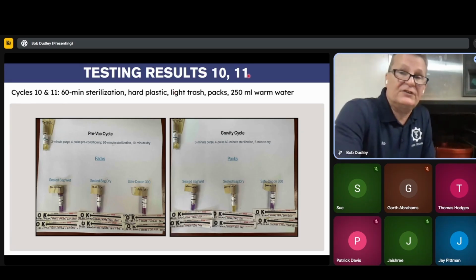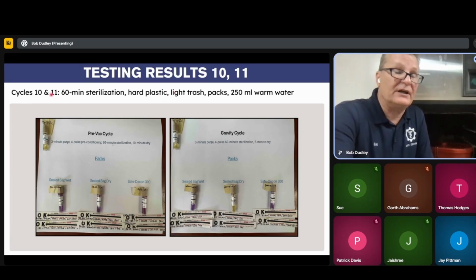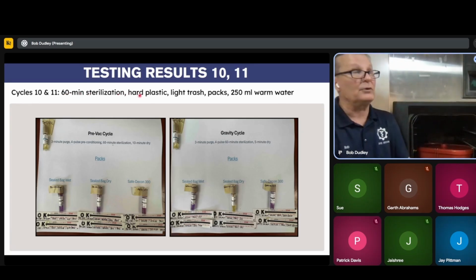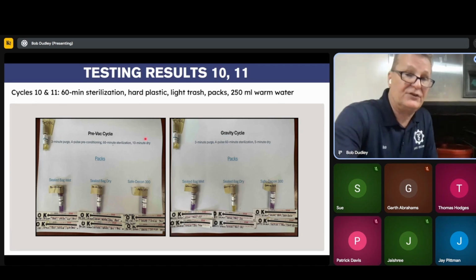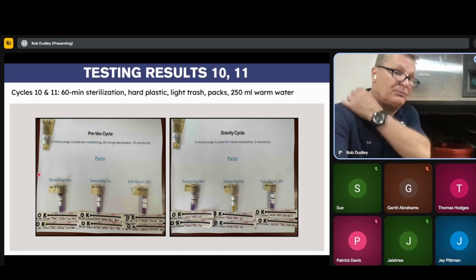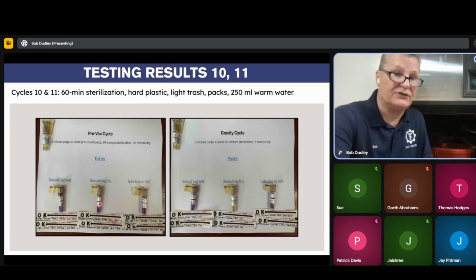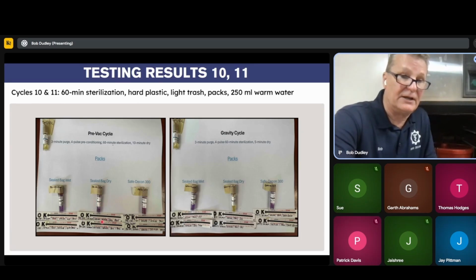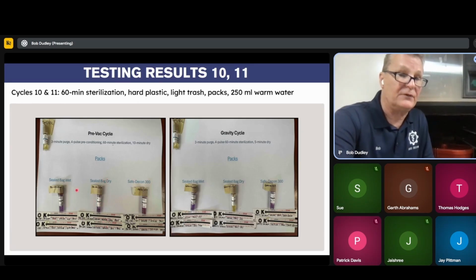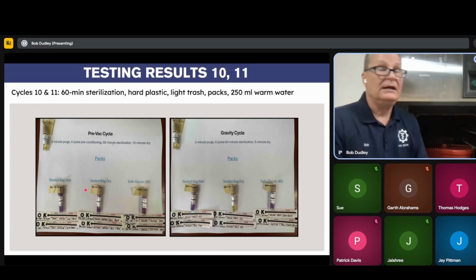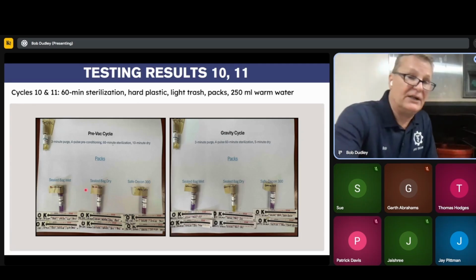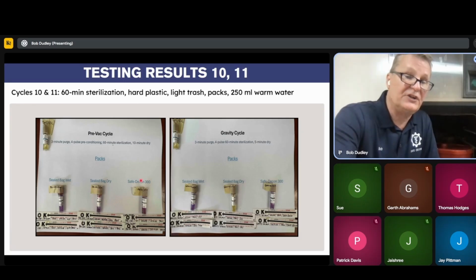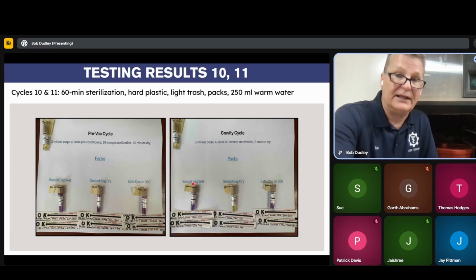What I did for test 10 and 11 is I increased the amount of water, but I increased the time to 60-minute sterilization. A lot of people run 45 to 60 minutes. On the pre-vac, both of these did bust over time. We did get your chemical strips, all three made it through. These bags, all these did bust. Where they busted, they probably busted a little early in the cycle, which allowed them to get it. 60-minute, we got the kill. Safe-Decon again.